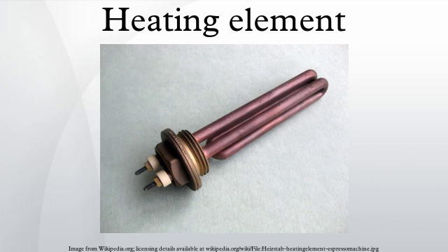Metal heating elements, Nichrome. Most heating elements use Nichrome 80/20 wire, ribbon, or strip. Nichrome 80/20 is an ideal material, because it has relatively high resistance and forms an adherent layer of chromium oxide when it is heated for the first time. Material beneath this layer will not oxidize, preventing the wire from breaking or burning out.